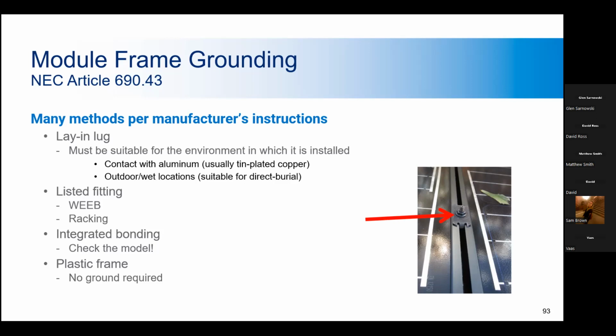Now, some solar panels have plastic frames and don't need to be grounded. But you still have to make sure that there's a good bond path through the system. At the array, the bonding and grounding are very important. It provides the pathway for fault current to open an overcurrent protection device or to be detected by the fault detection equipment, which will disconnect the fault from the system.